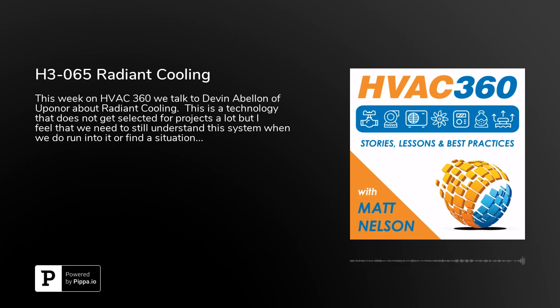And then, as we monitor indoor relative humidity, we're calculating dew point. Really, what the control system is trying to do is optimize the system so that it's supplying the right supply water temperature to maximize the effectiveness of that slab while ensuring that we don't get too cold and don't cause surface condensation. It sometimes sounds a little complex, but at the end of the day, it's a number of temperature sensors, an indoor relative humidity sensor, and a slab sensor all working together to manage that slab.